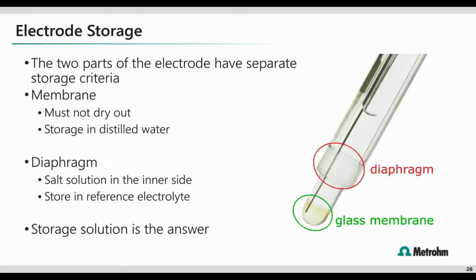This formula is specially designed to quench both of those. So we provide enough hydration for the glass bulb and enough salt to keep the diaphragm moving. Additionally, it has some added antifungal properties, and this will help prevent algae growth and contamination if the electrode is stored for extended periods of time.